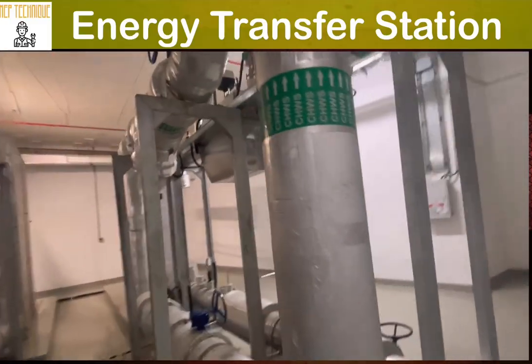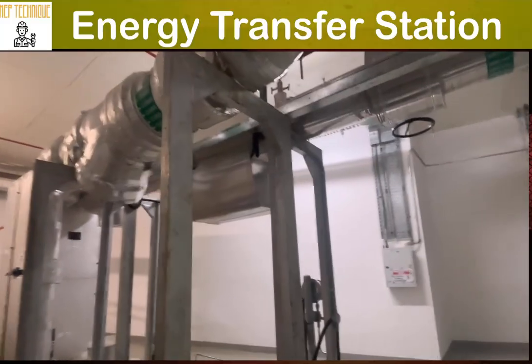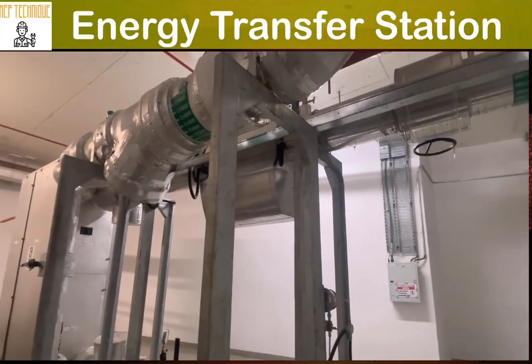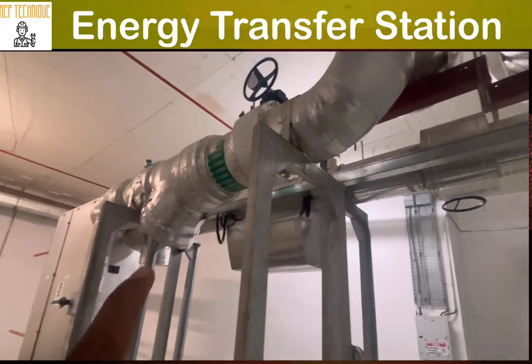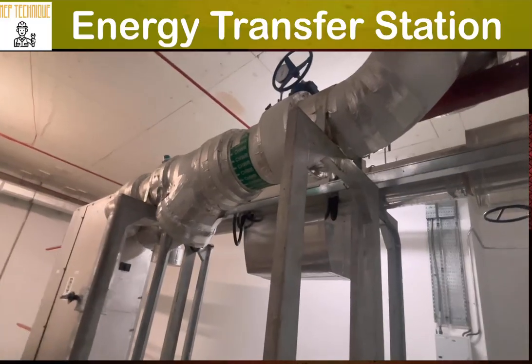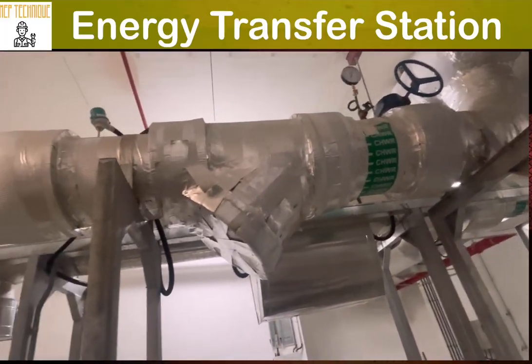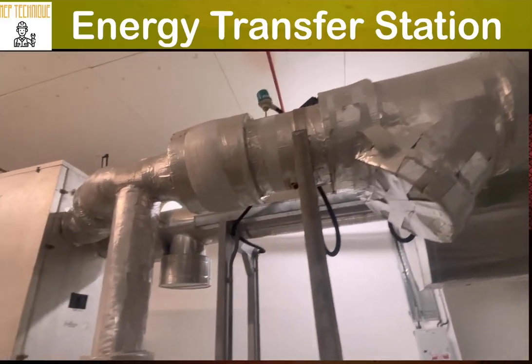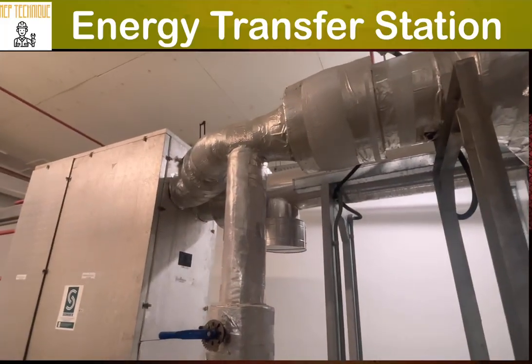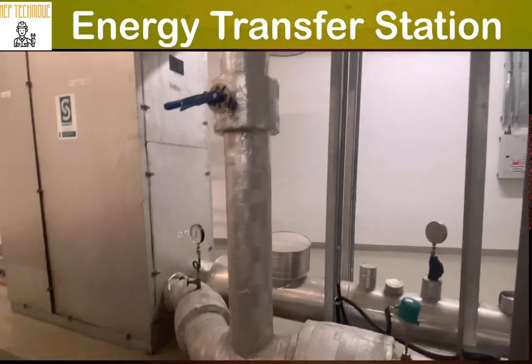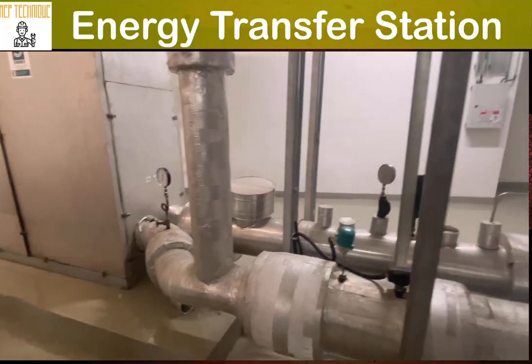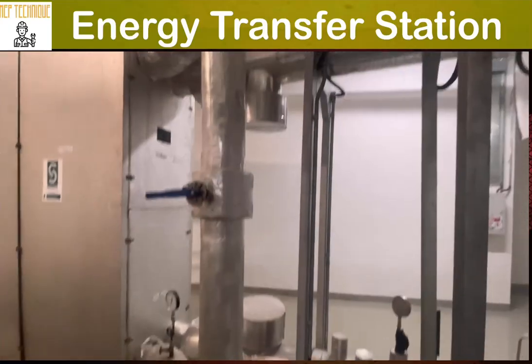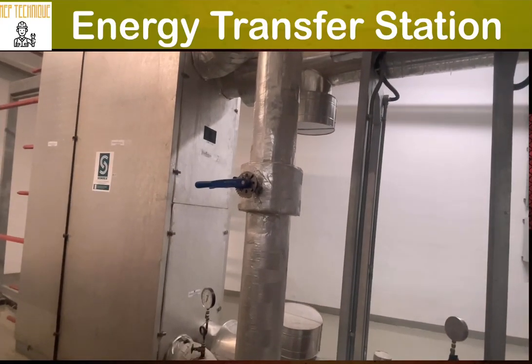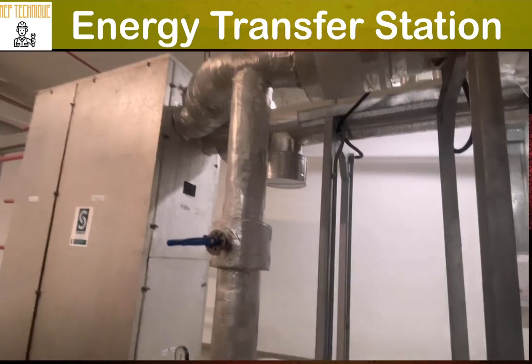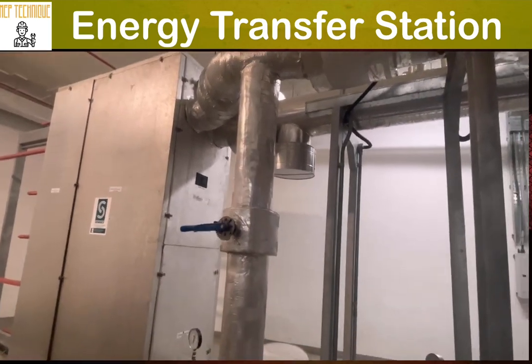Counter flow means the distribution company pipe is connected at the bottom of the chilled water, where our building line is connected at the top of the chilled water from our building equipment, such as AHU, FCU, whatever the equipment. So this is our building line, and here it is going to our building. You can see there is a bypass valve. In the event of any emergency or maintenance, you can bypass the chilled water.